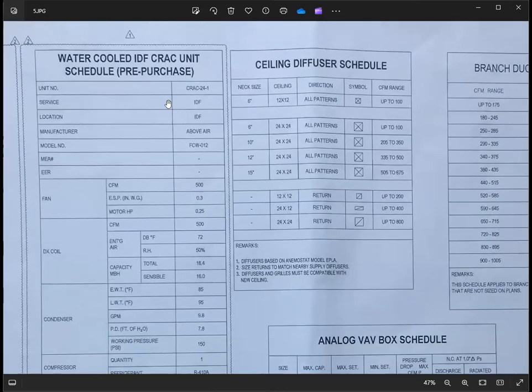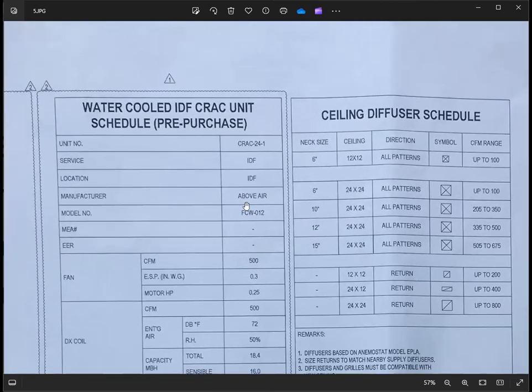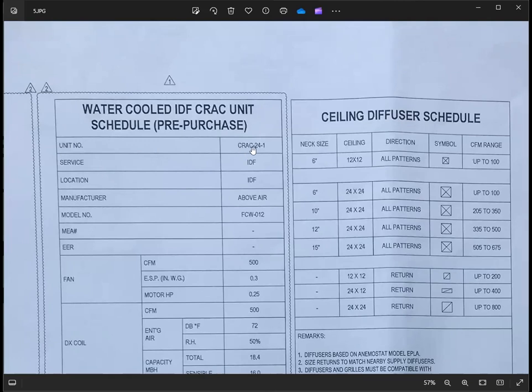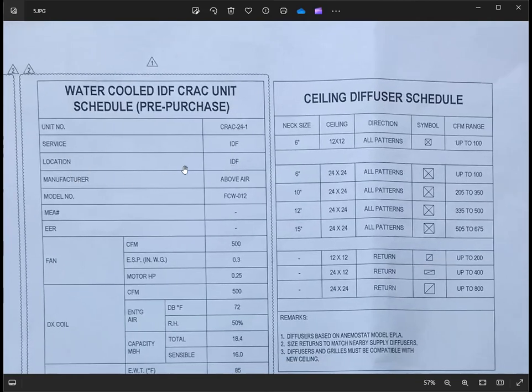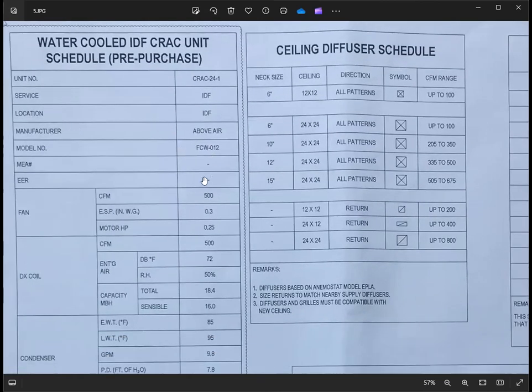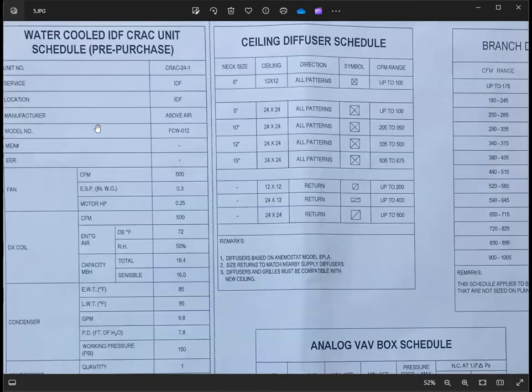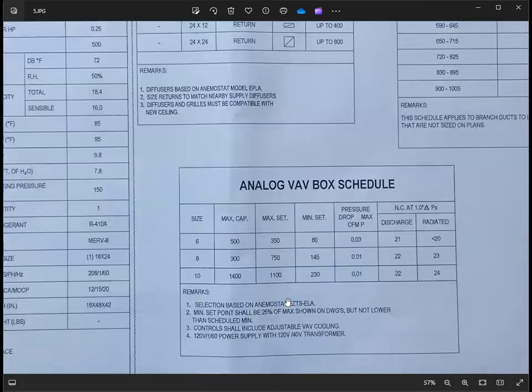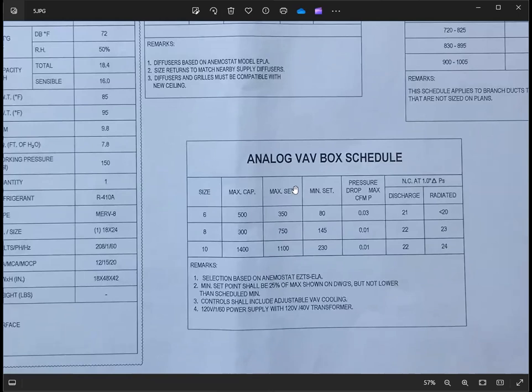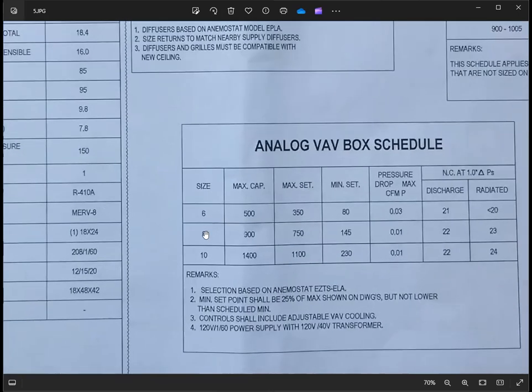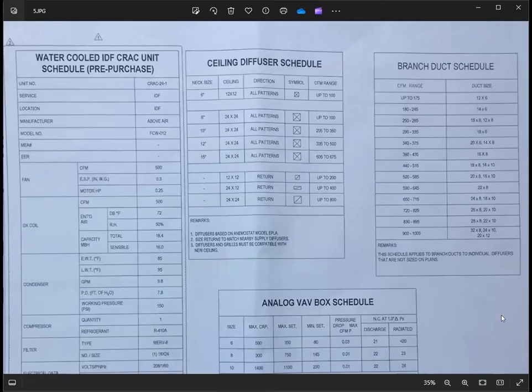And then this is the equipment mechanical schedule for the equipment they can install. So you have to identify, verify and match what was specified in the drawing. So this is the designation, the CRAC dash 24-1, and the location, IDF, manufacturer and model number. So take note of this and see if you're gonna have a matching manufacturer and model number. And this is the specs for the VAV box, the variable air volume box. So we need to identify the sizes that should be installed on the drawing plan, and some other duct schedules, ceiling diffusers, and take note of the drawing number.